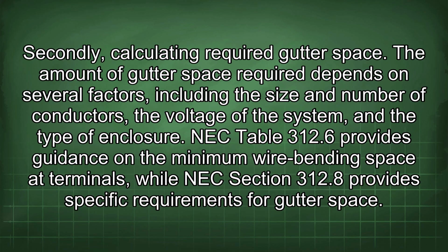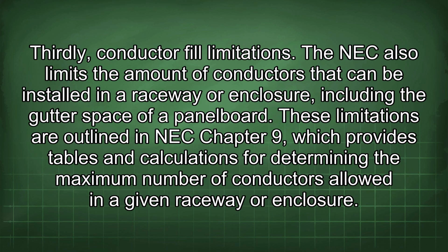Secondly, calculating required gutter space. The amount of gutter space required depends on several factors, including the size and number of conductors, the voltage of the system, and the type of enclosure. NEC Table 312.6 provides guidance on the minimum wire bending space at terminals, while NEC Section 312.8 provides specific requirements for gutter space.